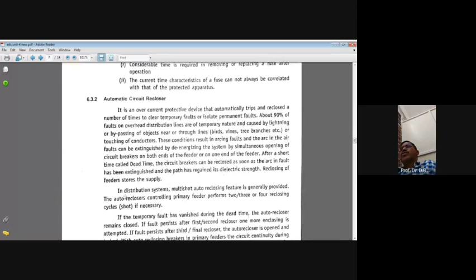This is the automatic circuit recloser. It is an overcurrent protective device that automatically trips and recloses a number of times to clear temporary faults or isolate permanent faults. About 90% of faults on overhead distribution lines are of a temporary nature, caused by lightning, or by an object bypassing near or through lines, such as tree branches touching a conductor. These conditions result in arcing faults, and an arc in the air can be extinguished by de-energizing the system by simultaneous opening of the circuit breakers on both ends of the feeder.